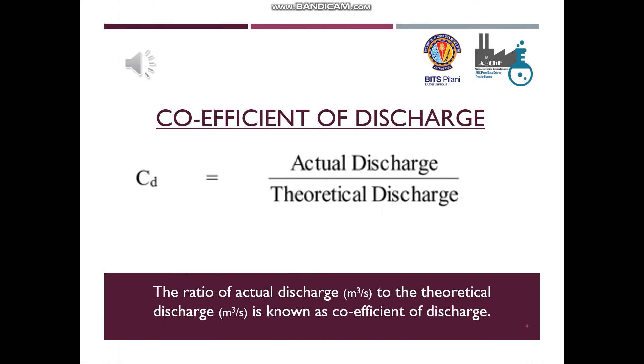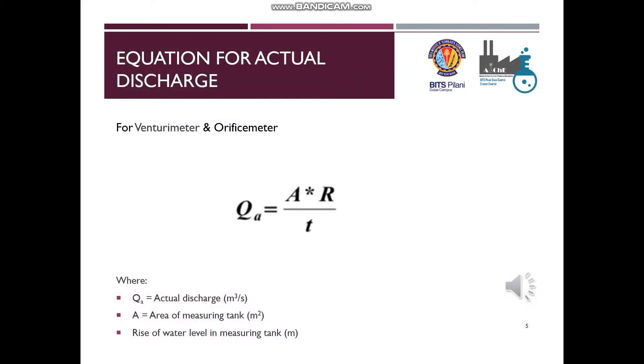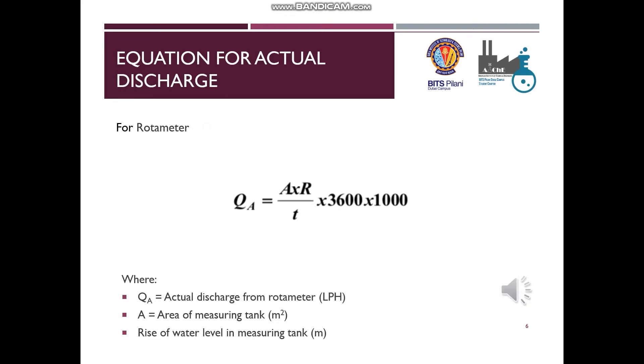Now let us see how to calculate the rate of actual discharge. First, we must define what a coefficient of discharge is — it is the ratio of actual discharge to the theoretical discharge. For a venturimeter and orifice meter, the actual discharge equals the product of the area of the measuring tank and the rise of water level, divided by the time taken. For a rotameter, the same formula applies but the result is multiplied by 3600 and 1000.